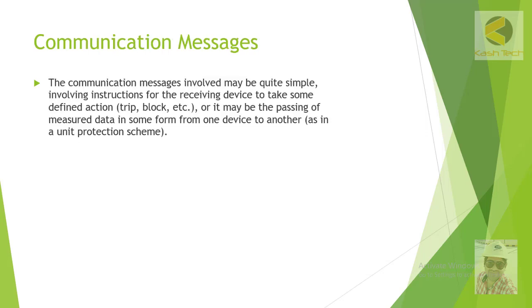Communication messages involved may be quite simple, involving instructions for the receiving device to take a defined action such as tripping or blocking, or it may involve passing measurement data from one device to another as in a unit protection scheme. For example, in line differential protection, current measurements from both ends are communicated — so the signal could be a trip signal, a blocking signal, an unblocking signal, or measurement data.